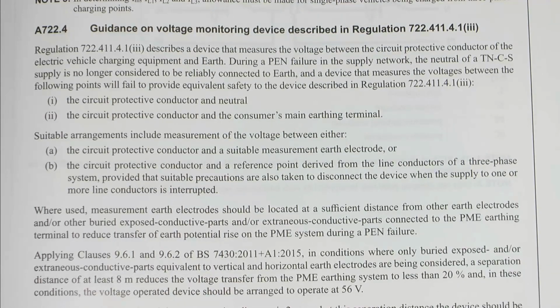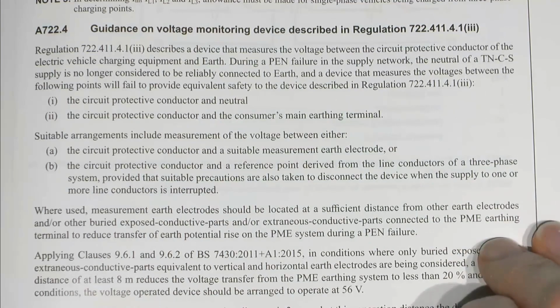So that's measuring the voltage between the circuit protective conductor neutral and the circuit protective conductor and the consumer's main earthing terminal. And the reason it won't work is on a TNCS supply, the protective conductor and neutral are connected together at the origin of the installation, so there won't be a voltage difference between them because obviously they're connected together. And the same applies to the protective conductor and the consumer's main earthing terminal because again they're connected together, so they would be at the same voltage. So that's why that won't work.